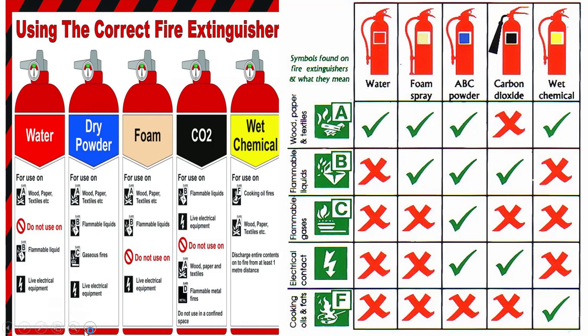Using the correct fire extinguisher is very, very important. For Class A fire, use water. Foam spray can be used for Class A and Class B. ABC powder can be used for Class A, Class B, Class C, and even for electrical fire. For wet chemical, you can use it for Class A fire and kitchen fire.